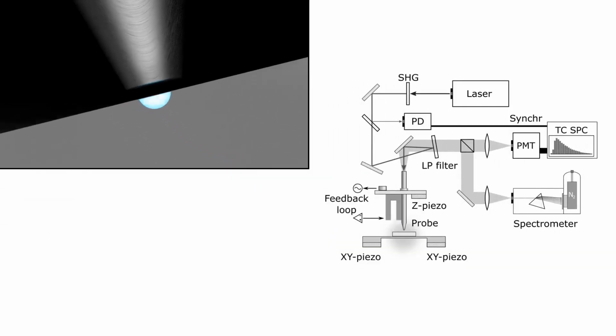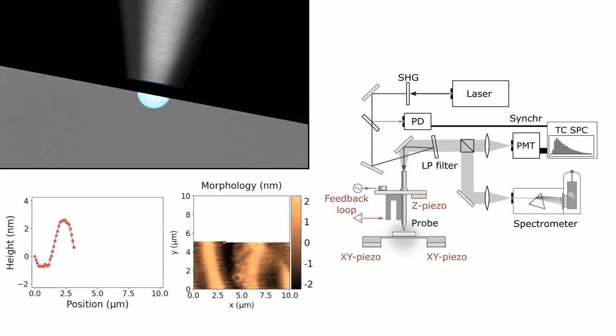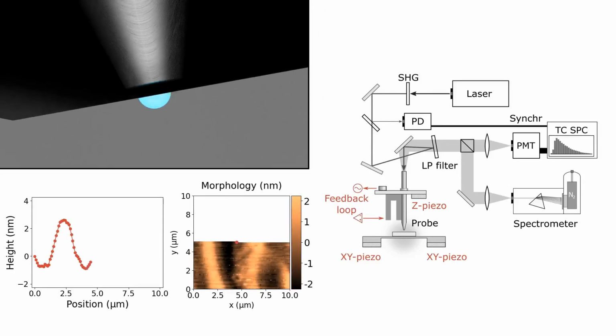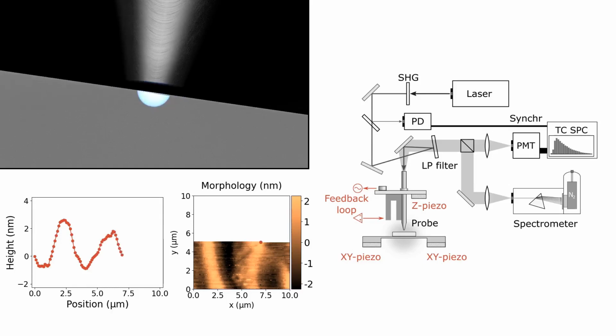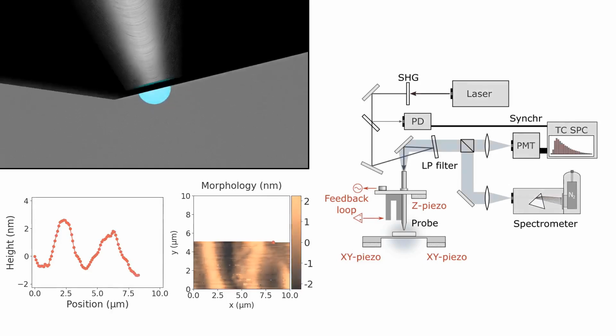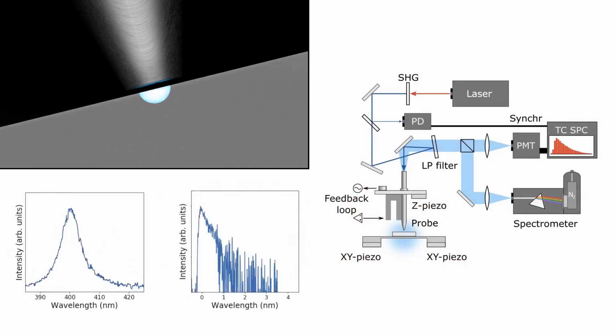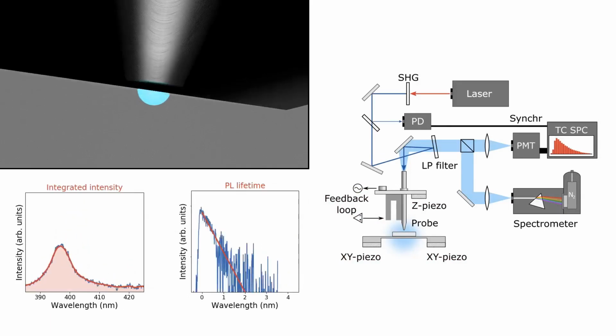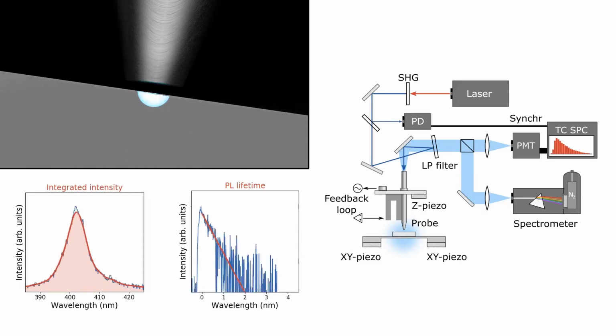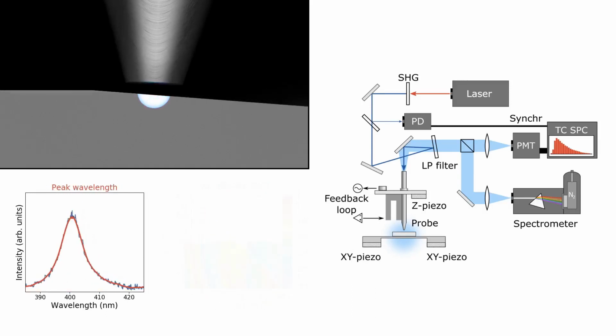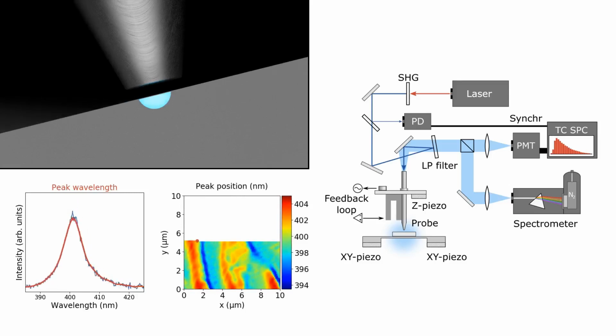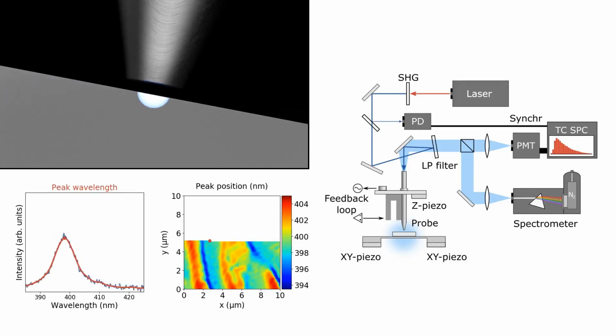Using a feedback loop, the probe-to-sample distance is controlled, which allows us to measure the morphology. The optical signal is then collected back through the probe aperture and analyzed outside using a time-correlated single photon counter and spectrometer, which then allows measuring different optical properties and, for example, taking the photoluminescence peak wavelength spatially mapped.